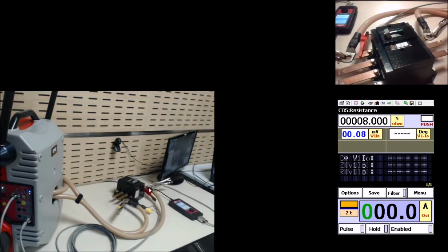That's it. And now select one amount of current on the commander here. Okay, I just adjust, for example, 100 amp. Enable the output and start. So you can see that the Raptor is injecting 100 ampere right now across this phase in the circuit breaker, which is closed, and stops the test, giving me a reading. What's the impedance on this connection? Okay, in this connection, I have an impedance of 519 micro ohms.